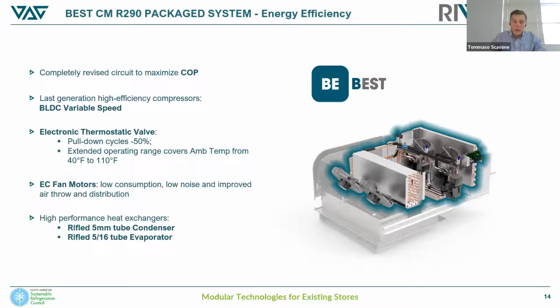The electronic expansion valve also allows us to extend the operation of our monoblock from ambient temperatures up to 110 F to a minimum of 40 F, so bringing lower consumption when closer to these critical conditions. The new electronic fan motors, fitted as standard again on both evaporator and condenser side, besides leading to important energy consumption savings, also have a low noise impact and are positioned to guarantee greater airflow and fast air distribution, improving the overall performance of the unit.